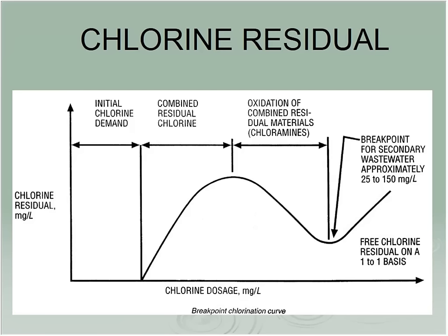So what's happening through here, okay, I'm going to add chlorine. I've still got some bacteria in there. I haven't removed all of my solids. I've got some other components, maybe a little bit of metal or something like that. I put chlorine in and I see no chlorine at all. It's forming chlorides, it's breaking down other materials. Once those are gone, I'm going to get some combined chlorine.